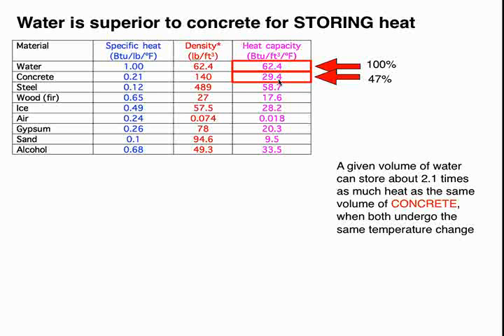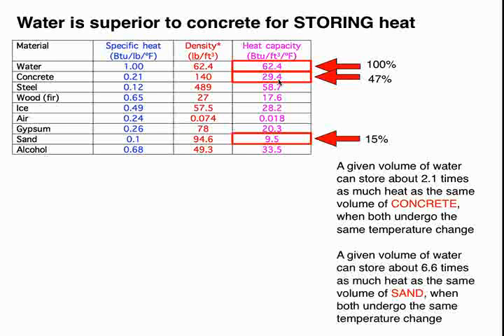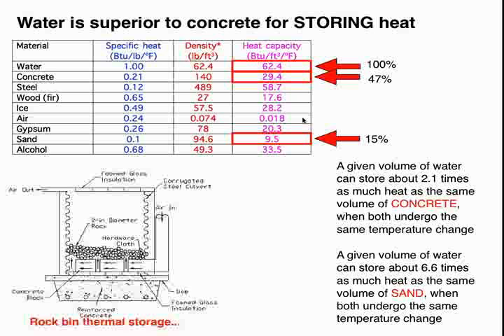And I've had questions over the years, wouldn't concrete be a better material to store heat in compared to water? And actually, from a volume standpoint, it shows you that water has about twice the heat storage capacity of concrete on a volume basis. So water is a good material. Another question that will come up occasionally, what about sand as a storage material? And actually, if you compare the heat capacity of sand, you can see it's quite a bit lower than either concrete and substantially lower than water. So yeah, sand can store some heat, but it's not in the same league as water is when it comes to heat storage.